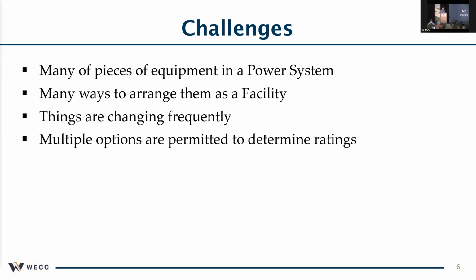And then multiple options are permitted. As you know, if you look at requirements 1, 2, and 3, you can use nameplates. You can use a method that's been approved by the IEEE. You can use a test. You can use an engineering evaluation, or you can use historical performance. All those are acceptable ways to determine facility ratings. Now, auditors really prefer the nameplate rating, but all of those are acceptable. But if you're not clear in your methodology, it's a free-for-all. So you've got to specify which one of those you will use and which one you won't.